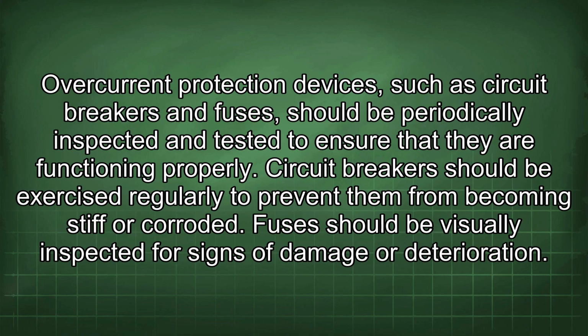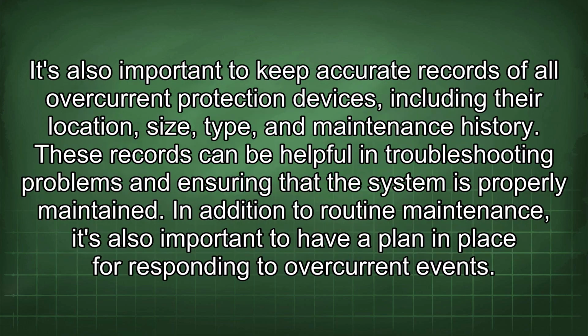Overcurrent protection devices, such as circuit breakers and fuses, should be periodically inspected and tested to ensure that they are functioning properly. Circuit breakers should be exercised regularly to prevent them from becoming stiff or corroded. Fuses should be visually inspected for signs of damage or deterioration. It's also important to keep accurate records of all overcurrent protection devices, including their location, size, type, and maintenance history. These records can be helpful in troubleshooting problems and ensuring that the system is properly maintained.